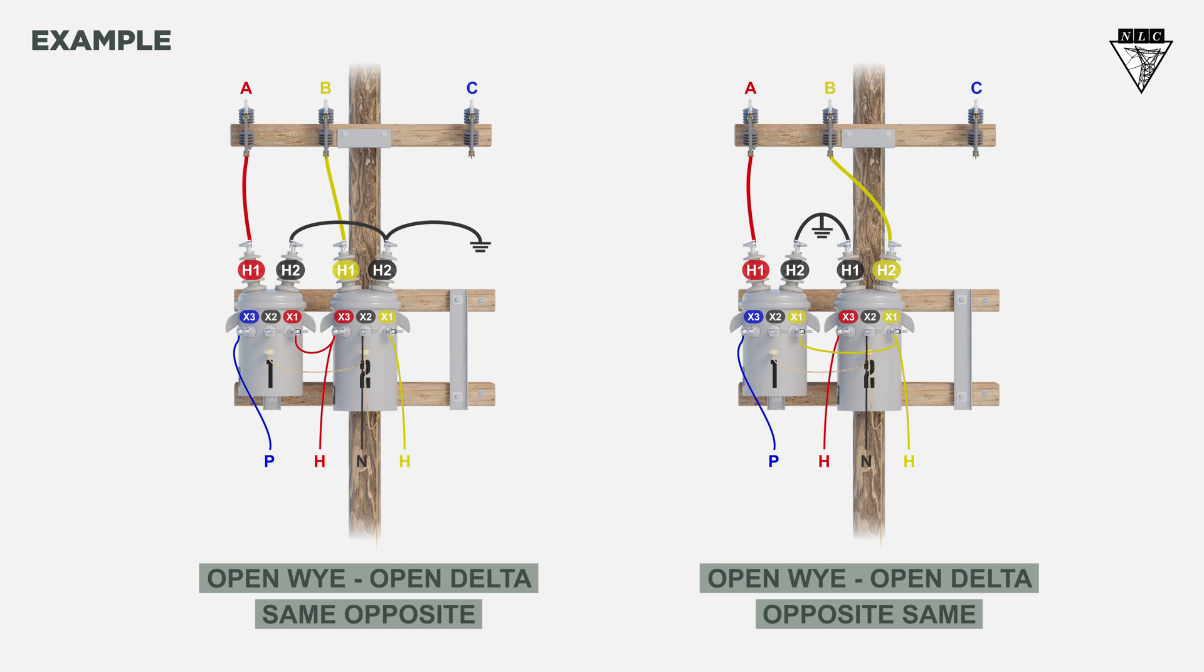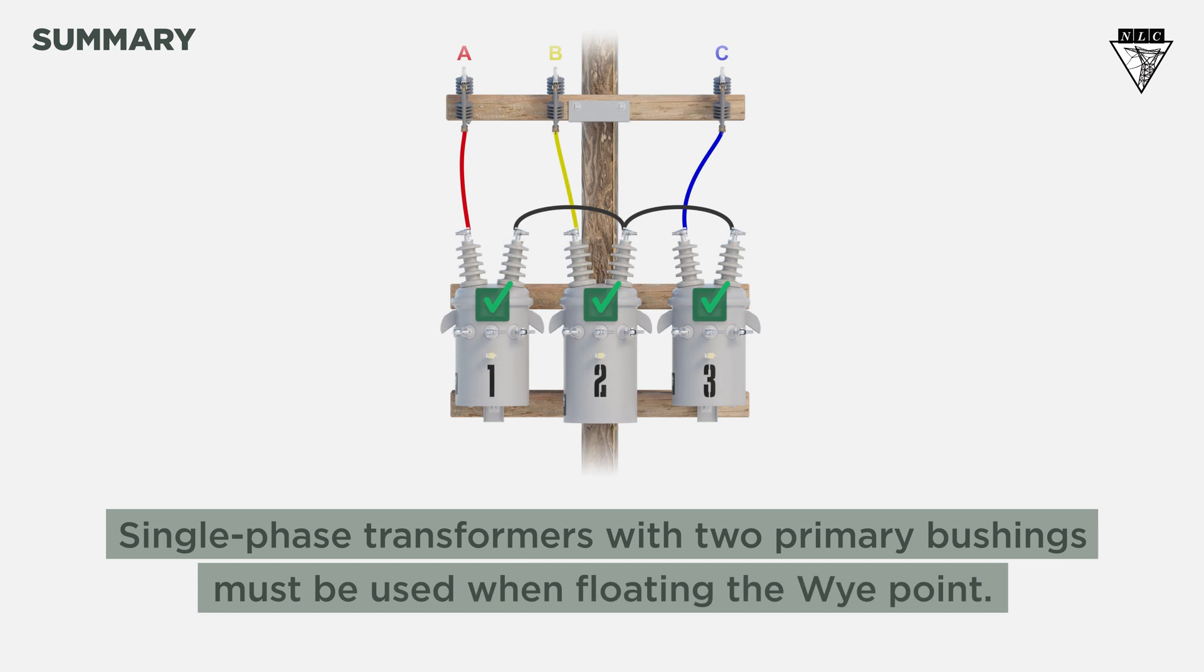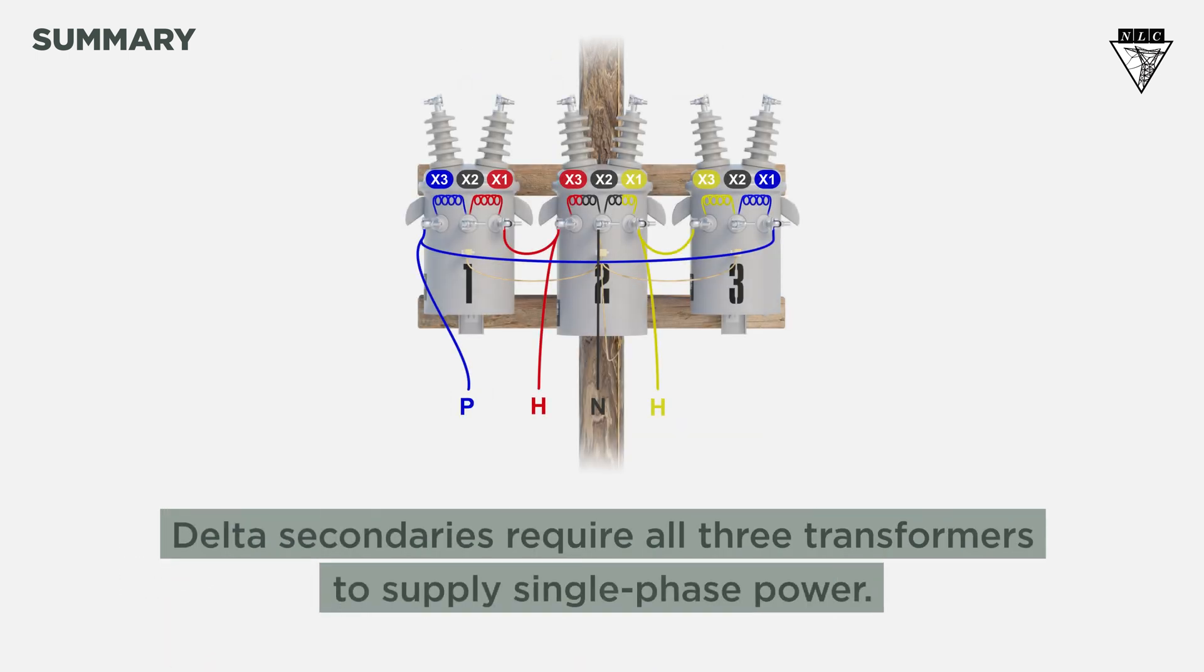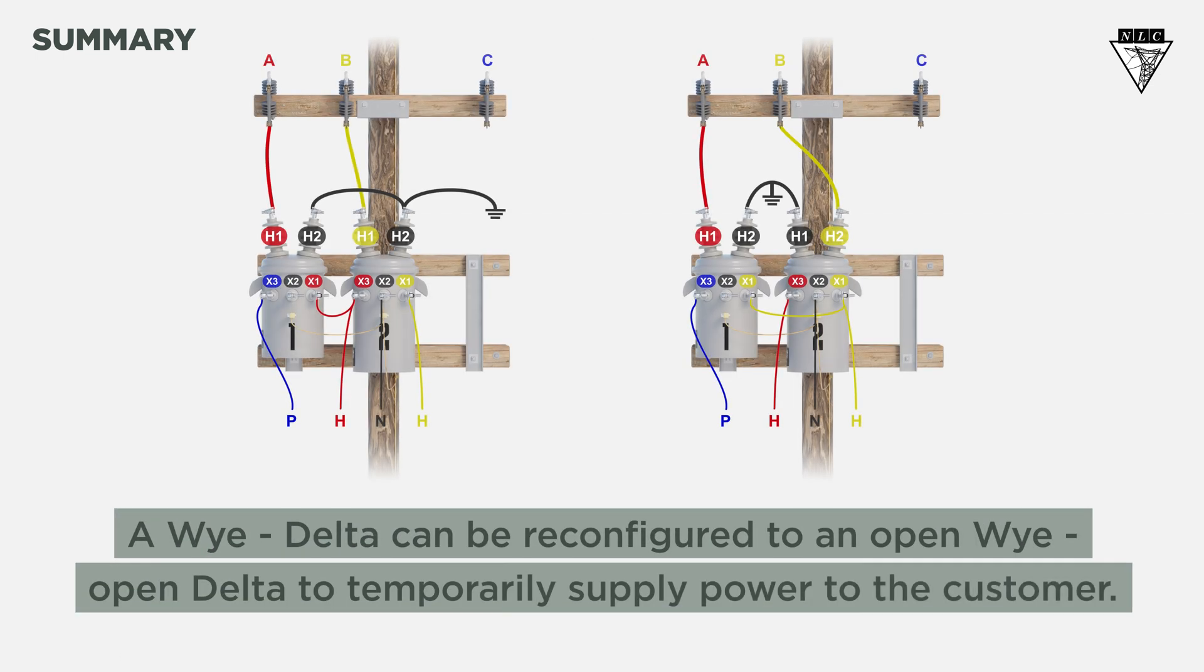So, what did we learn? Single-phase transformers with two primary bushings must be used when floating the Y-point. Delta secondaries require all three transformers to supply single-phase power. A Y-delta bank can be reconfigured to an Open Y Open Delta to temporarily supply power to the customer.